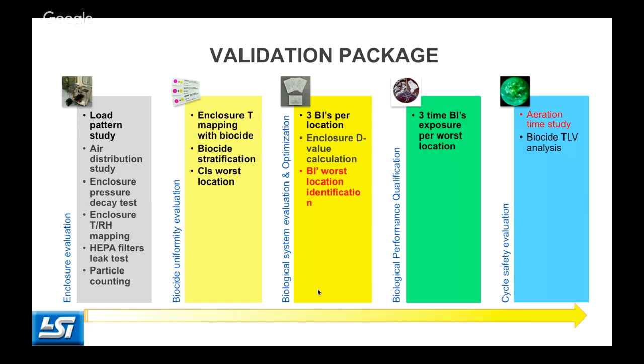Also, we make air distribution studies with the smoke in order to check this load pattern. We need to validate the enclosure pressure decay test. So we need to be sure that the enclosure is airtight. Leak can occur. Making temperature relative mapping of the enclosure. Of course, as well, a HEPA filter leak test, and also particle counting, because we can guarantee an ISO 5 at rest condition inside the chamber.